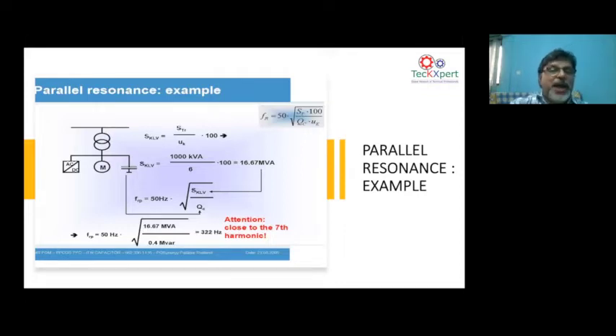That means when you add a capacitor to a network, you have to be extremely careful. You should not just think of improving power factor just like that. You should always check whether, when I'm adding the capacitor, it affects parallel resonance in the network. Where should I install this capacitor bank so that the resonance is avoided? So those aspects have to be looked into whenever you design a capacitor bank in an environment where there are a lot of harmonic producing loads.